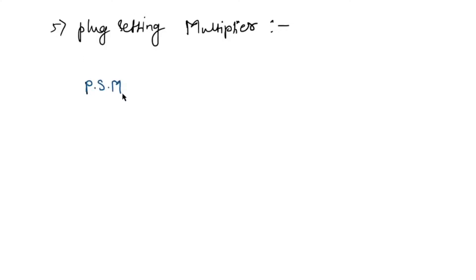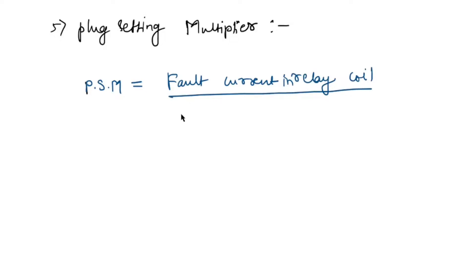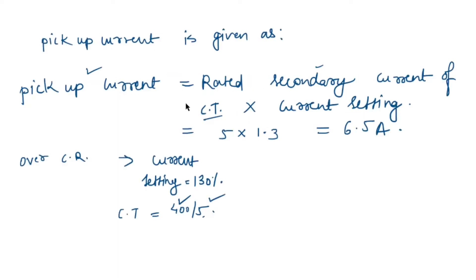The next terminology is plug setting multiplier, or PSM. PSM is defined as the ratio of the fault current in the relay coil to the pickup current. The formula is: fault current in relay coil divided by the rated secondary current of the CT multiplied by the current setting.